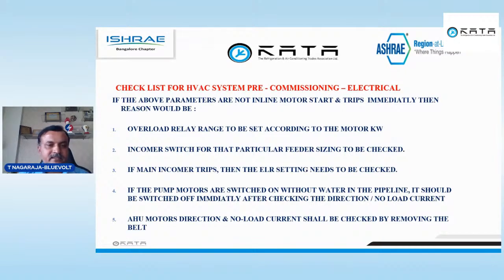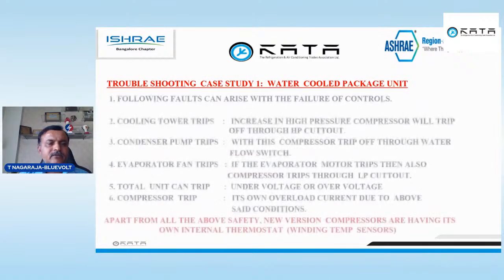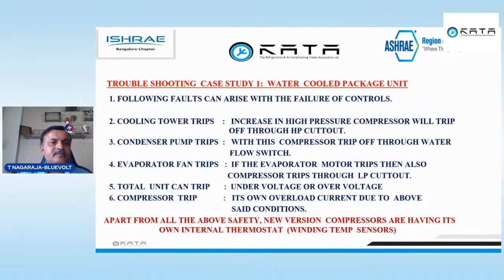So please check that. If the pump motors are switched on without water in the pipeline, they should be switched off immediately after checking the direction or no load current. AHU motors direction and no load current shall be checked by removing the belt. I think nowadays belts are not there, all plug fans. Then troubleshooting case studies: I think I had given this with one picture. That picture is not there, but still I'll tell.